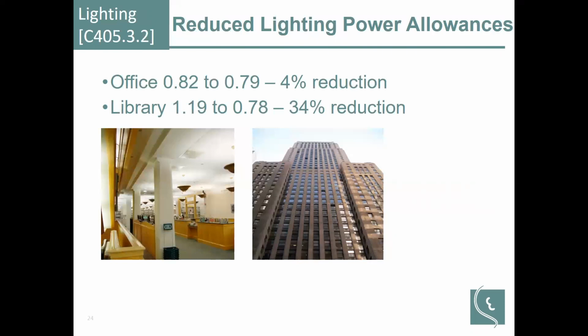One benefit of these lighting power allowances is when you are sizing your electrical service via the National Electric Code. Using energy conservation codes allows you to decrease the size of your service if you are under the provisions of an energy conservation code, assuming that additional provisions are met. So this can be a very big benefit of decreasing the service coming into your building, which is additional expense that you can avoid.